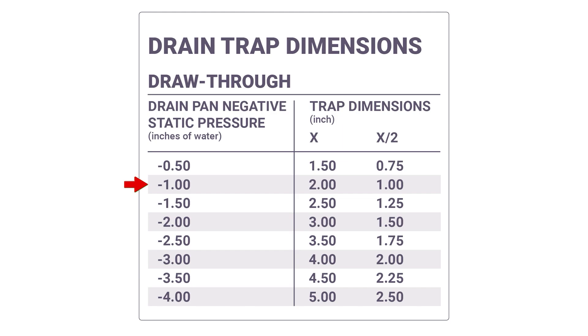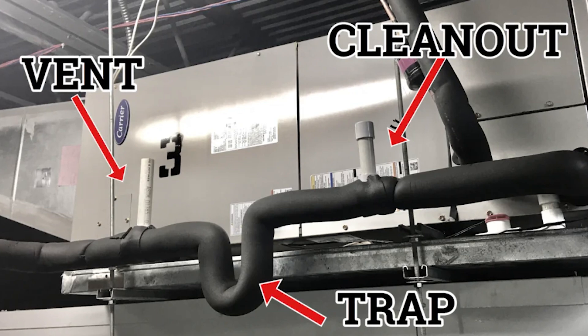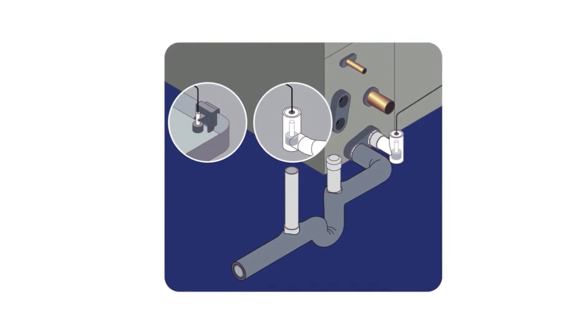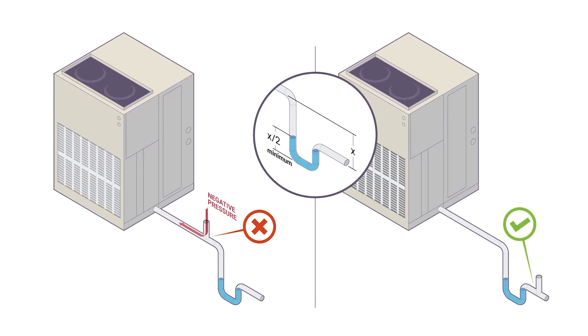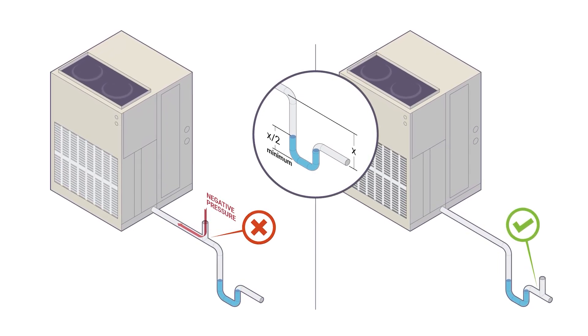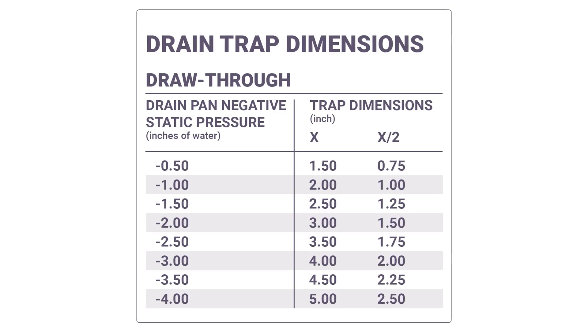For residential systems, a two-inch trap is about the most you'd ever need on a negative pressure system, because one inch of return-side water column would be so excessive you'd have massive system problems. One inch of return static is really pushing it — especially as the filter gets dirty or if you have high return static. Also keep in mind, we're talking about a standard P-trap with inlet and outlet — not a running trap or U-trap. The actual column of water held in the trap should be between one and two inches, with the size depending on how high you expect the return static to get.